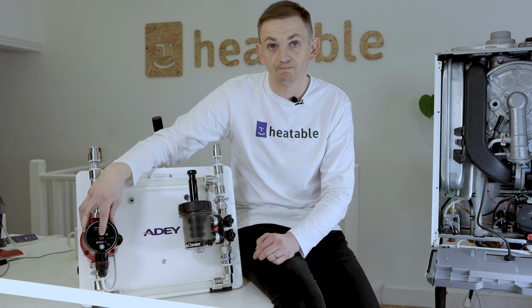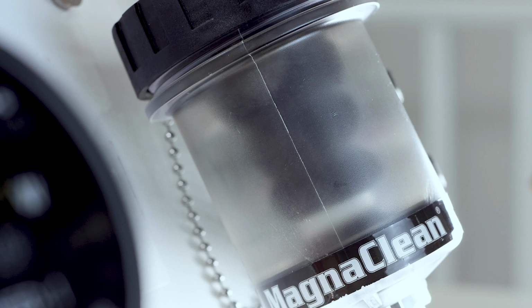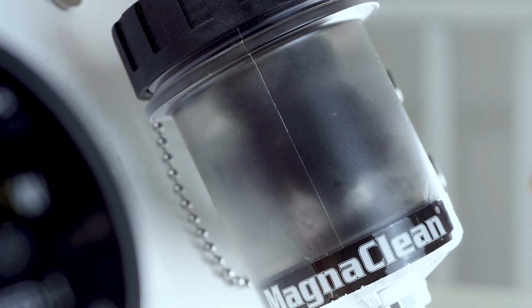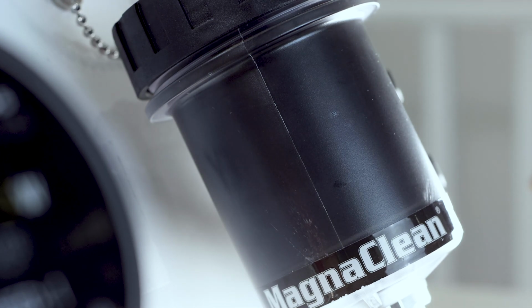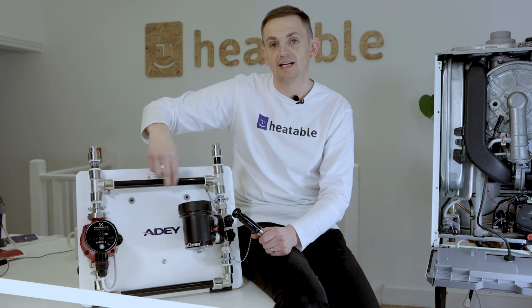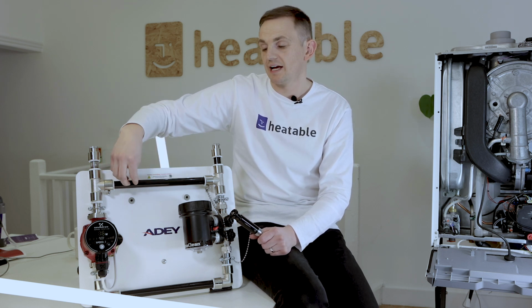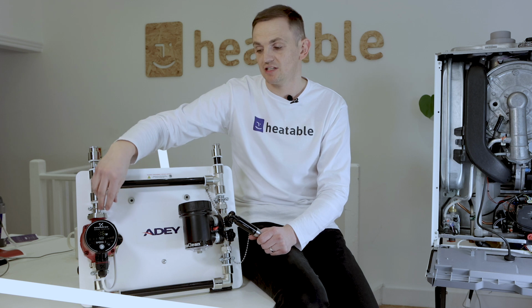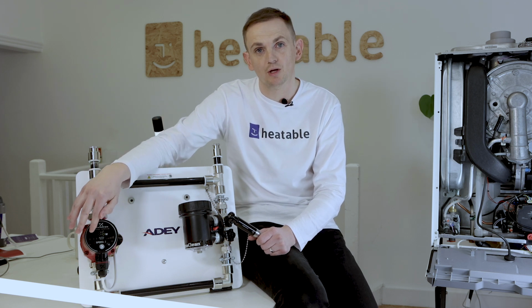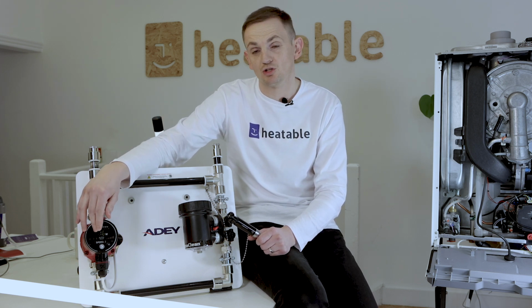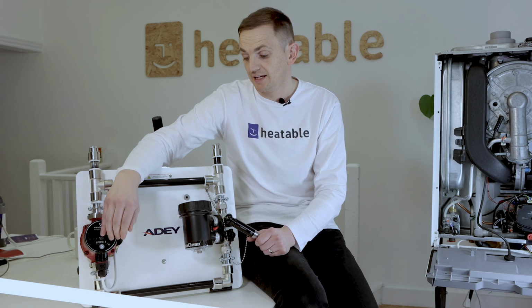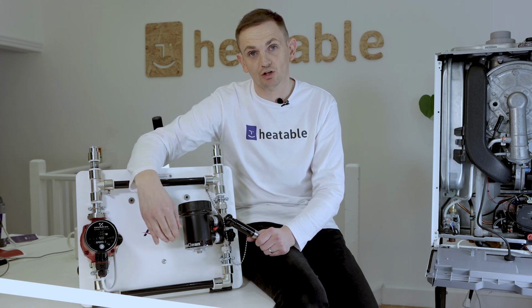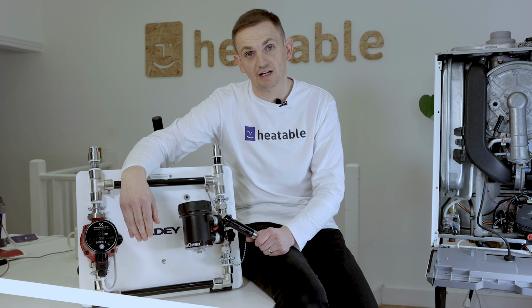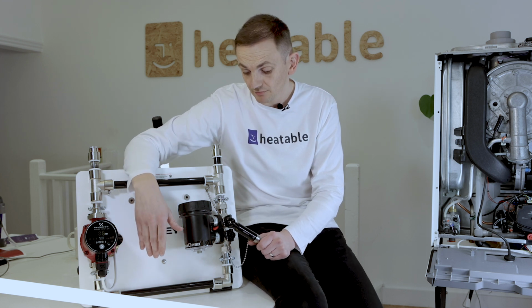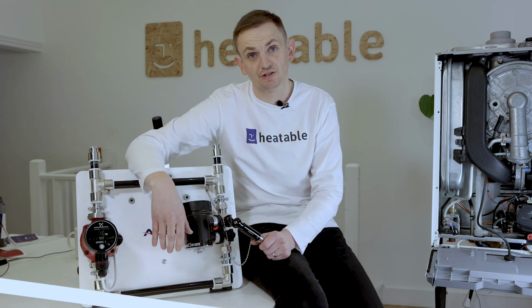The pump is running. We remove the magnet and the water instantly goes dirty. Now all this black water here contains magnetite. So unprotected, the magnetite is carried around the system. It goes through the pump, which puts extra demand on the pump, which uses more energy. It continues around the system, clogging up radiators, reducing radiator performance. And finally, it makes its way back to the boiler.